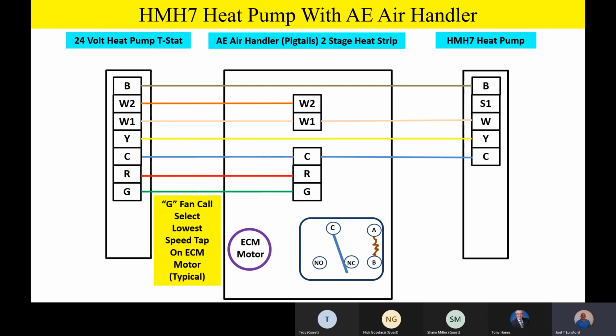Terminal is our fan call. That's very, very standard in the industry. So you have G from the thermostat right over to the indoor product. Now, before we start talking about how to wire that relay up, are there any questions or comments so far on our low voltage block wiring from our thermostat to the indoor unit to the outdoor unit so far?